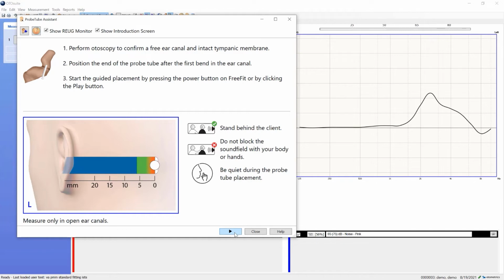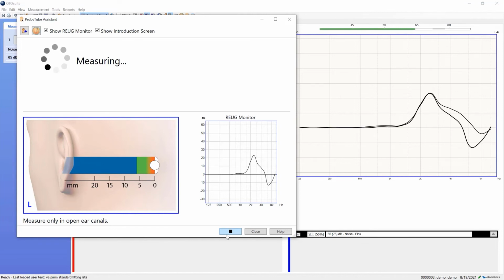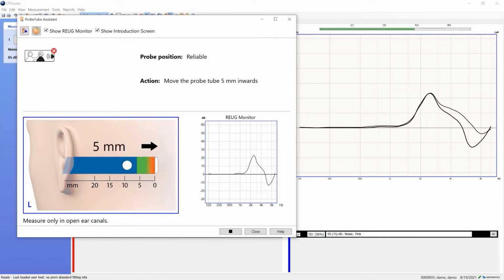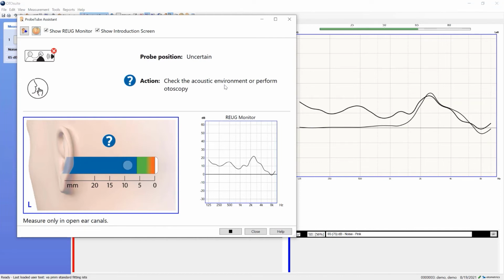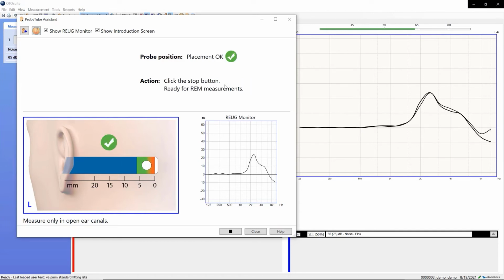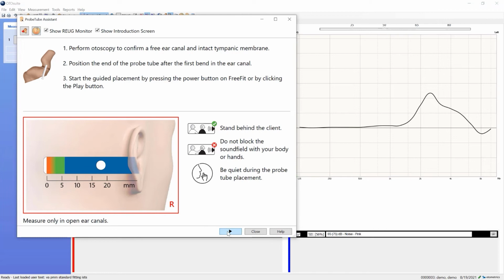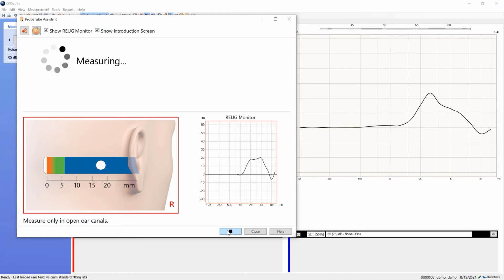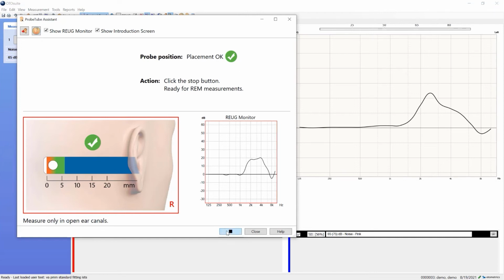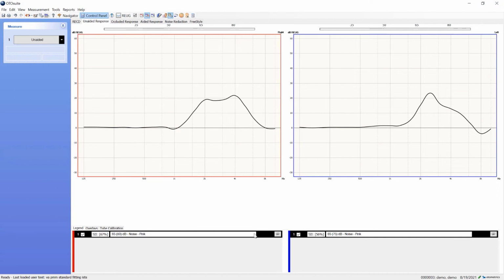The Probe Tube Assistant software will visually display the distance the probe tube is inserted and the remaining distance inward that's needed for proper placement. Press Start. In this example, the probe tube needs to be inserted an additional 5 mm. Gently move the probe tube inward until the green check mark appears, signaling you've reached the recommended probe tube insertion depth. Press Stop and repeat the process for the opposite ear. After achieving a green check mark for both ears, indicating proper probe tube placement, close the probe tube assistant and measure your unaided REUG or REUR as described earlier in this video.